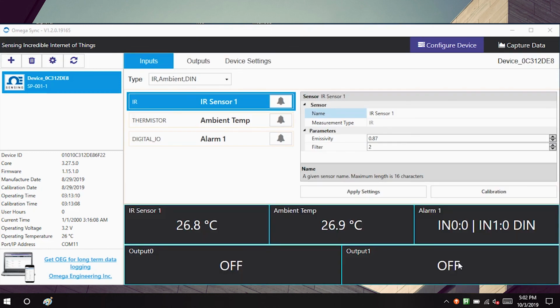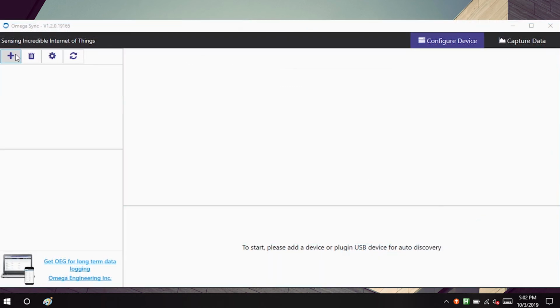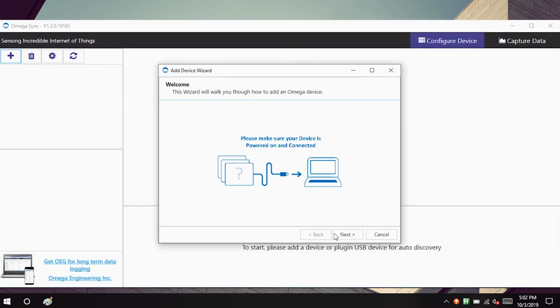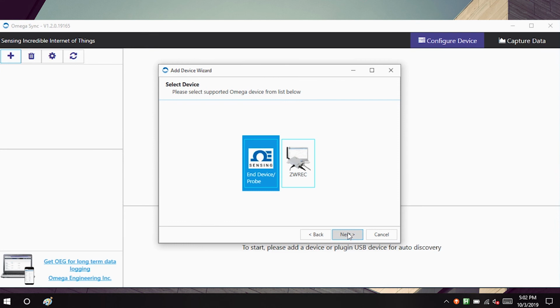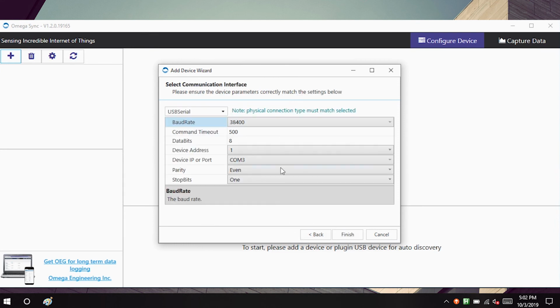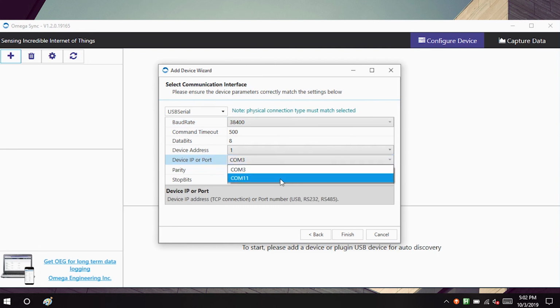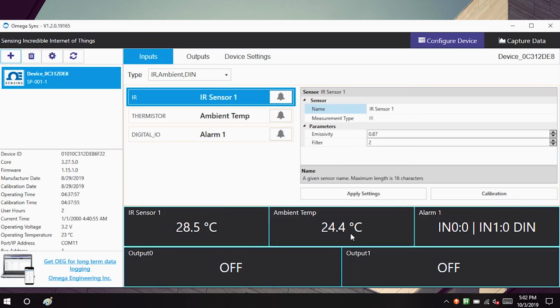If Sync does not automatically detect your smart sensor, click on the plus icon located at the top left of the Sync interface. Select End Device Probe and click Next. Select your communication interface type from the drop-down menu and set your preferred command timeout, device address, and device IP or port. Then click Finish and your smart sensor should start displaying temperature readings.